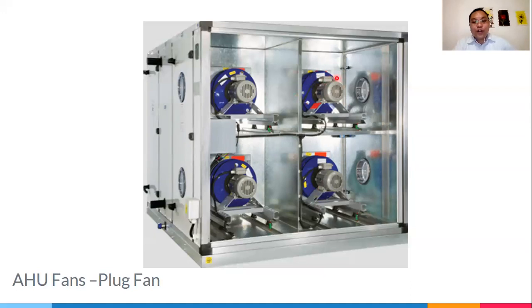So what happens is, when your fans are smaller, the electrical draw of your equipment is also smaller. You'll be able to have an overall smaller electrical requirement compared to a single centrifugal fan. So four small plug fans will have higher electrical efficiency compared to one big centrifugal fan.